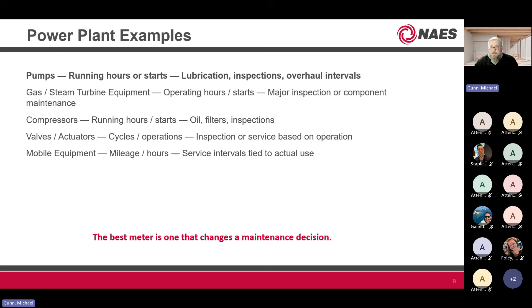So, potential benefits: I've already said it aligns with actual use. A lot of times switching over to meter based can reduce unnecessary PM activity. So many times we're going in and greasing a pump just because we said we're going to grease it every 3 months. There is such a thing as overgreasing. I've been told overgreasing can be as bad, if not worse, than undergreasing a pump.